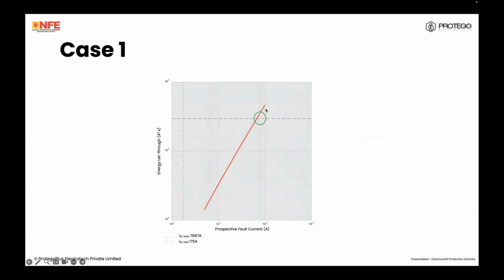Therefore, for faults towards the point of commencement of supply towards the circuit breaker, the cable will be damaged. The cable essentially cannot withstand the electrical energy caused by a short circuit. I'll give you an example.